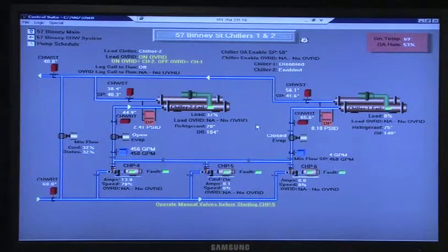Follow what I'm saying? If you understand two bundles, it's not an as-built of the system, I get it. It's just diagramming. It's diagrammatical, hey, it goes in the chiller, out the chiller. Unless they can put something in there showing the deviation with a line or something on the evaporator side and then the condenser side.